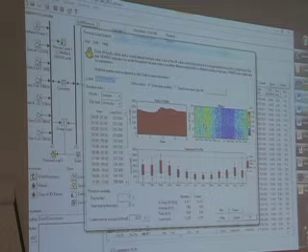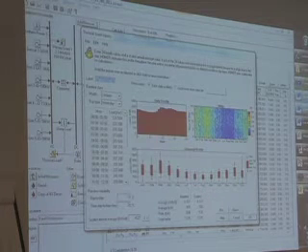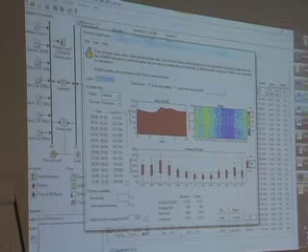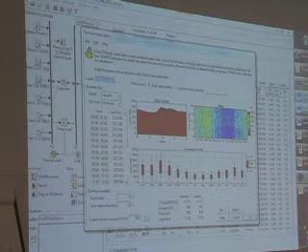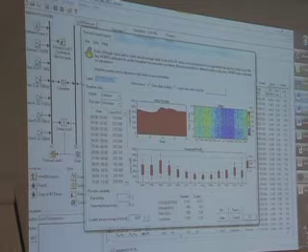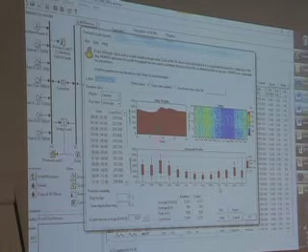Although I'm kind of curious, Cord, this struck me that the thermal load is higher in March than in January, but there's probably a reason for that, right? The 30-year climate data showed that yes, the highest demand of heating degree days was in the February-March timeframe. Really? Okay. So is this thermal load calculated based upon meteorological data or on some kind of boiler fuel measurement?